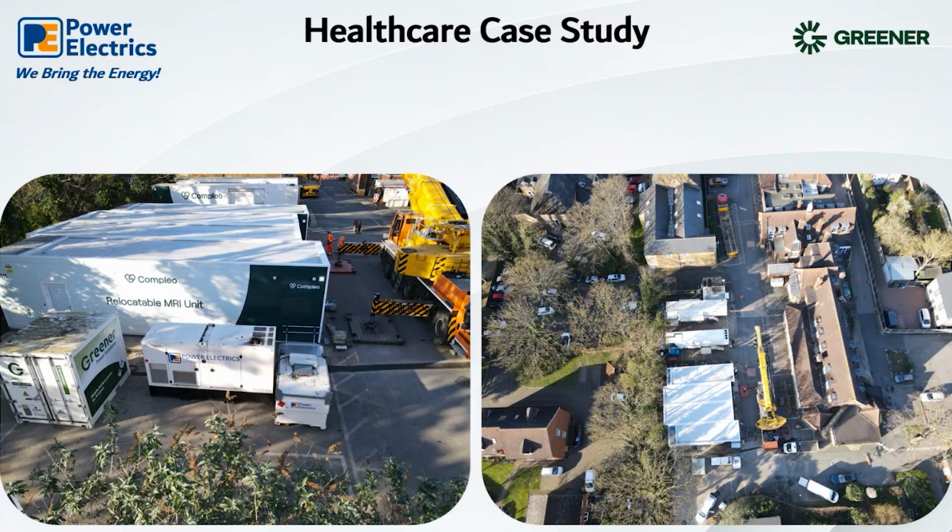Okay. And what advice would you give to customers to ensure that they're getting the most from their battery or hybrid setup? I think the main thing really is to understand how power is being used and energy is being consumed on site. Investigate how the overall load is made up. It's important to question electrical design calculations. I think a lot of electrical engineers are trained to specify power systems for grid connection, and therefore they follow the guidance which is suited to grid connected power systems, not necessarily temporary power systems.